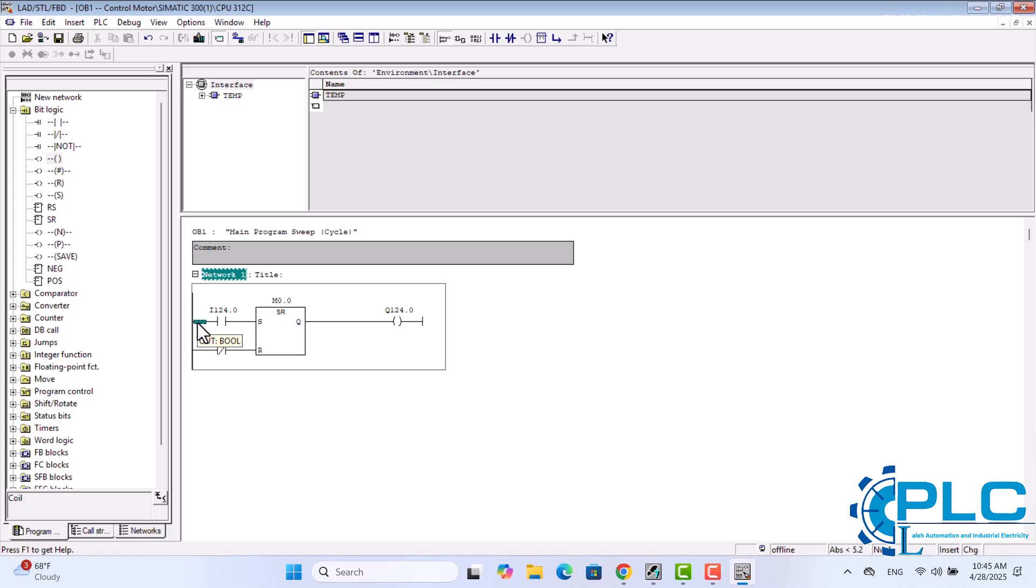In a previous lesson, we learned about parallel and series connections in ladder logic. Specifically, we saw that if we want to start the same action from two different buttons, we need to connect them in parallel. To add the second start button, I'll insert a normally open contact located at I124.2. I'll place this normally open contact in parallel with the first start button at the Set S input of the flip-flop.